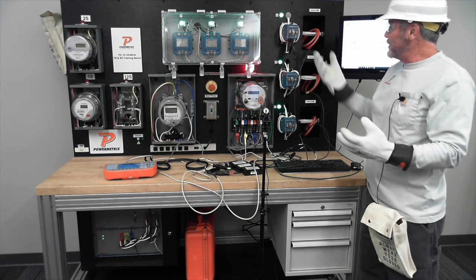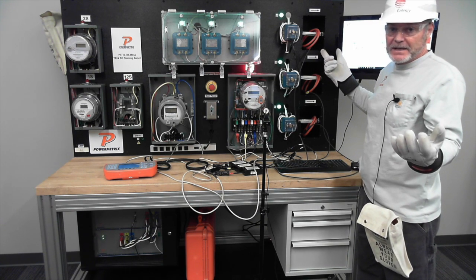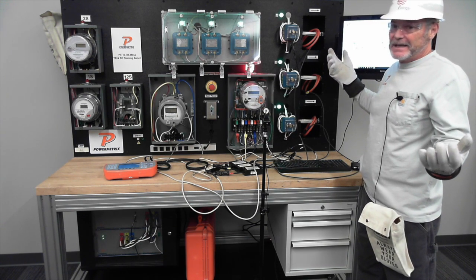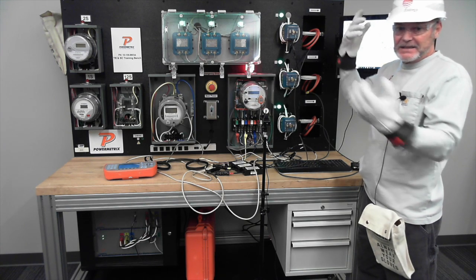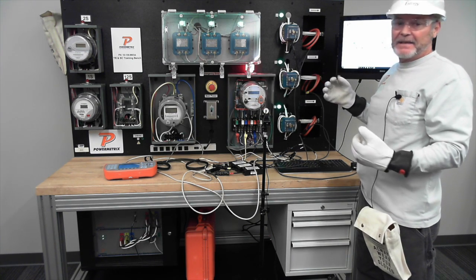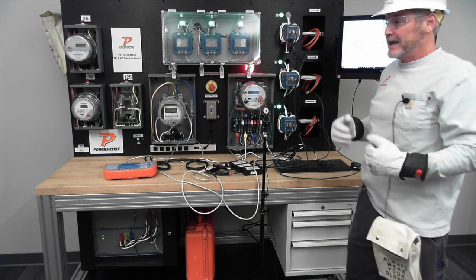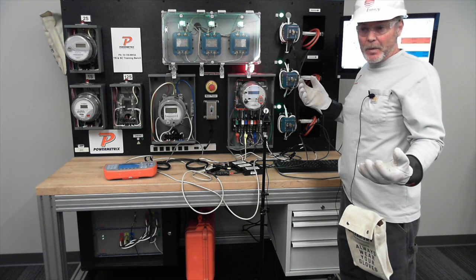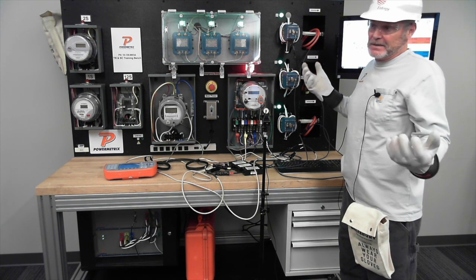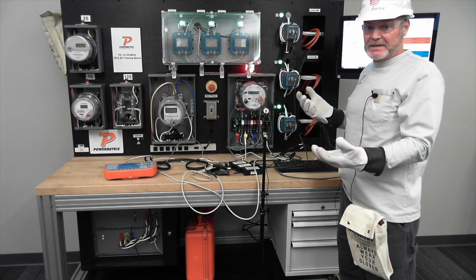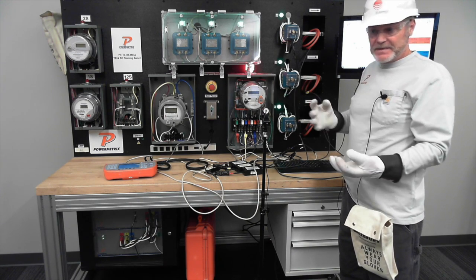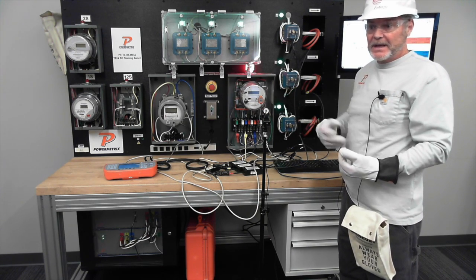Okay, because when I was at Dayton Power and Light that time, you probably heard that story. It was a 15 kV or 25 kV rack. It had CTs and PTs on it. Got hit by lightning. And they had it on a big rolling rack in there. And they were saying, I said, well, you going to do it? And they said, throw them away. I said, well, why? And they said, well, you know, it got hit by lightning. I said, well, have you measured them? They said, no. So I took the 7 series and I sat there and hooked the drive cable through it. And I just ran a test.